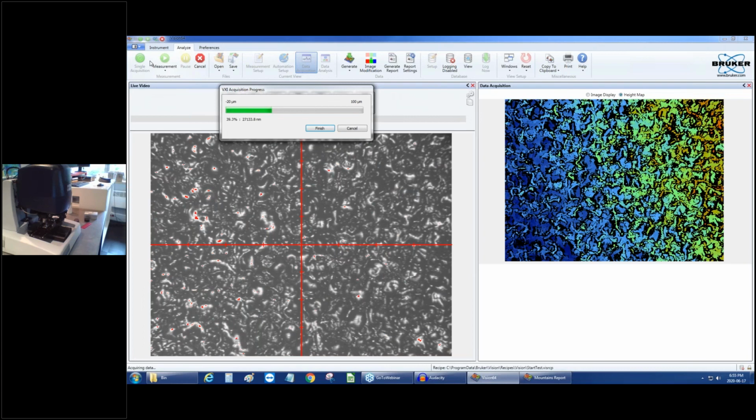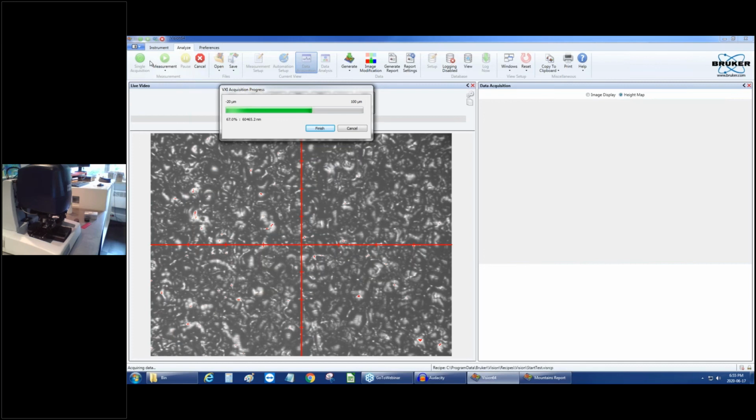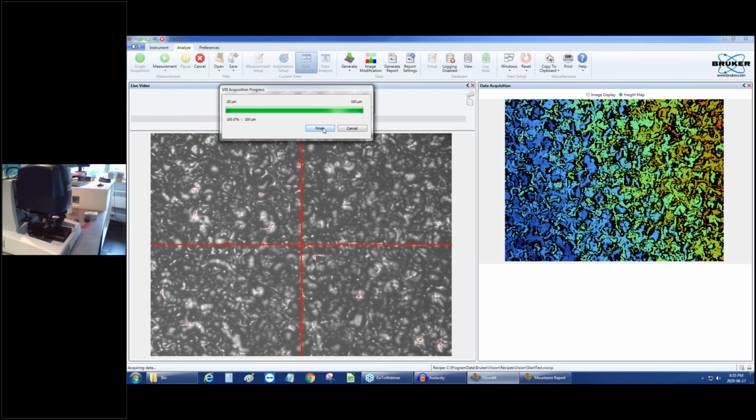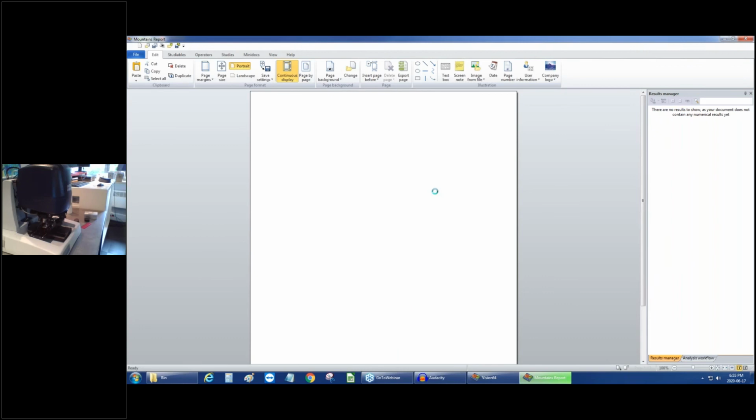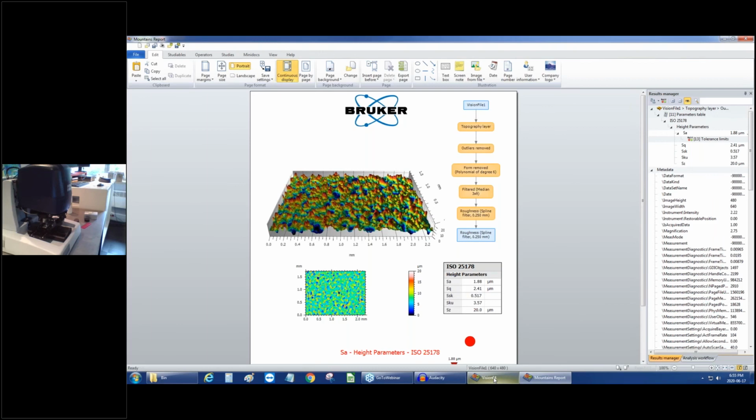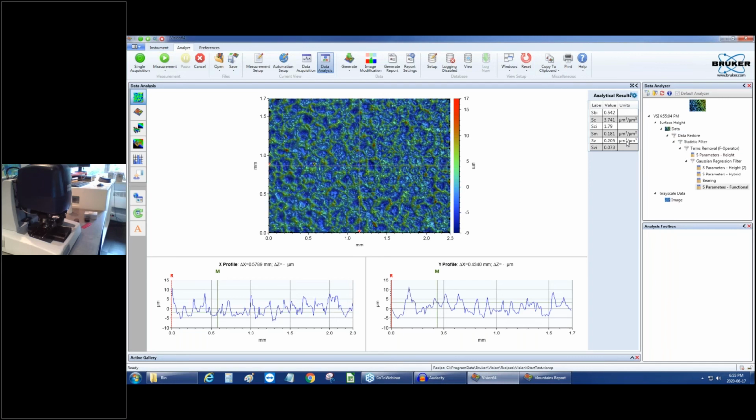And remember that with this technology of white light interferometry, I don't care about the objective I use, the vertical resolution will still be in a nanometer range or even lower. But in that case, you see everything is calculating back and takes, as you see, a certain amount of time to get out all the information calculated. And now once it's done, we can come back and see what kind of volume we have. So now you see the SV is much higher because we have a higher roughness, we have higher cavities. So this will be the wrong kind of surface for sealing, for instance, because there will be a leaking path over there that will make sense. So this is a way you can build and make your texture around.